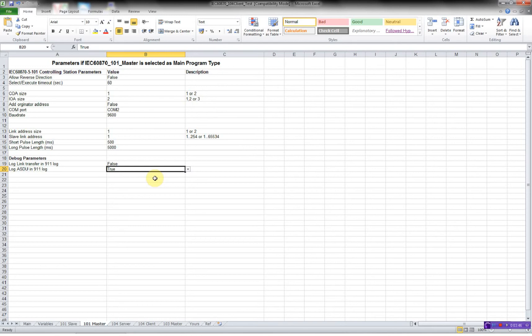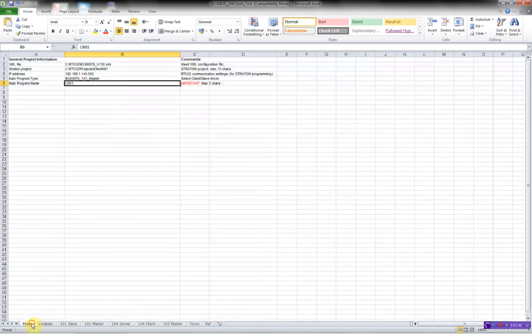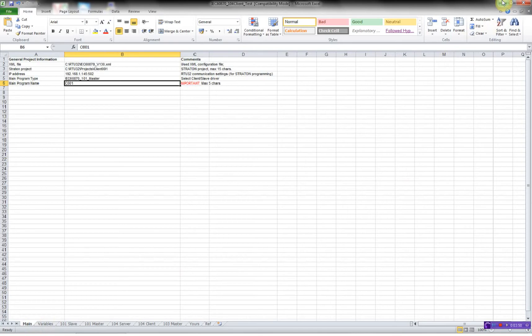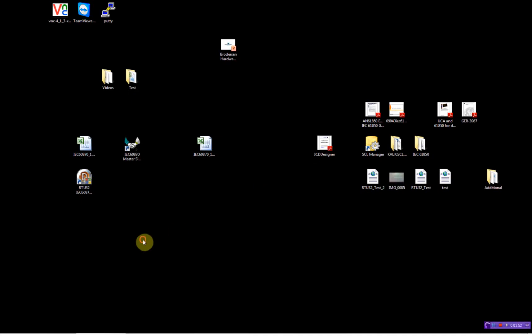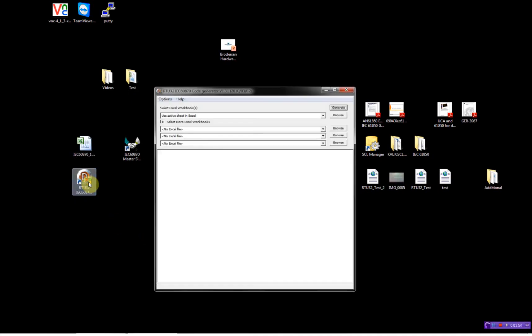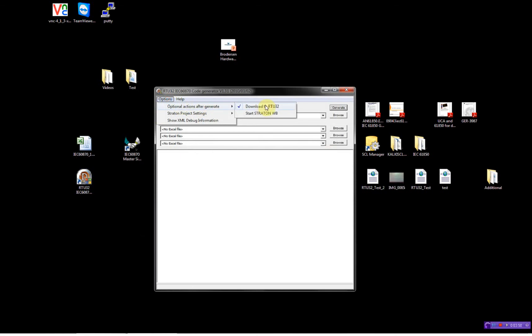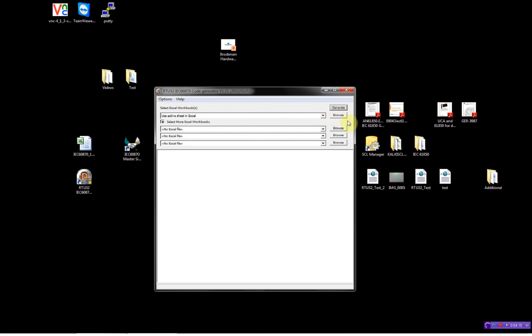So now we are done configuring our 101 master. We'll go to the code generator. Here I'll be choosing just to download the code directly after compilation. Then I have to choose whether I'll be using the active Excel sheet or I can browse for one. And I also have the opportunity to add several other Excel sheets. So I can program up to four RTU32 in one click.